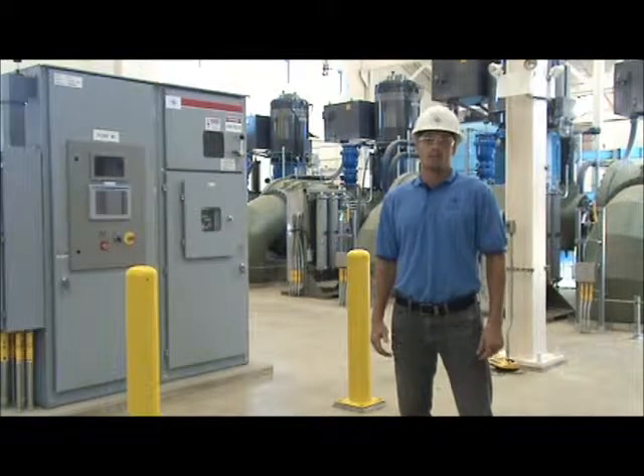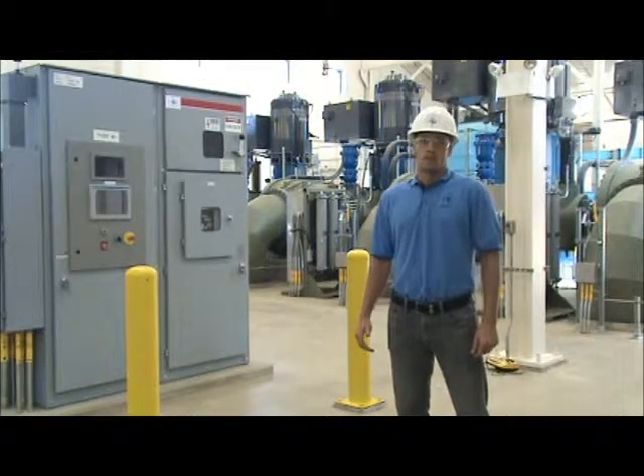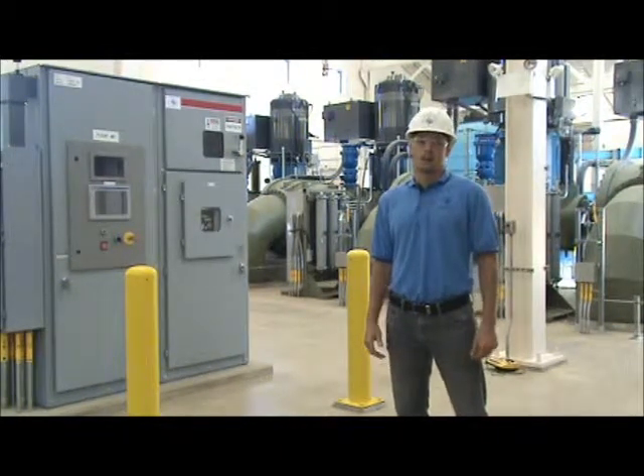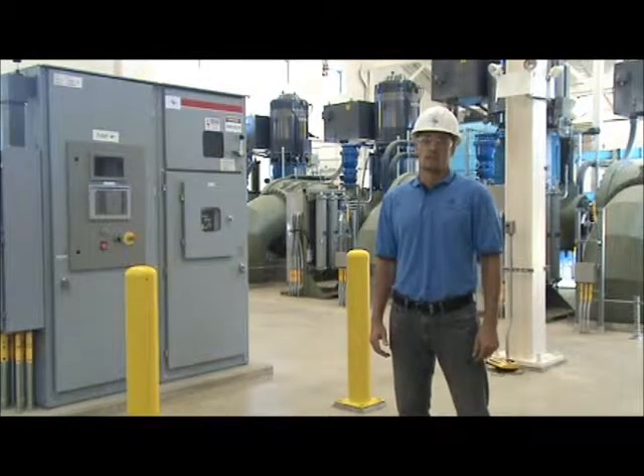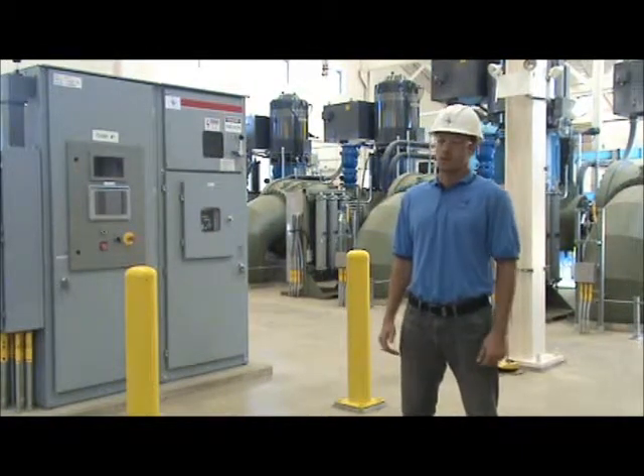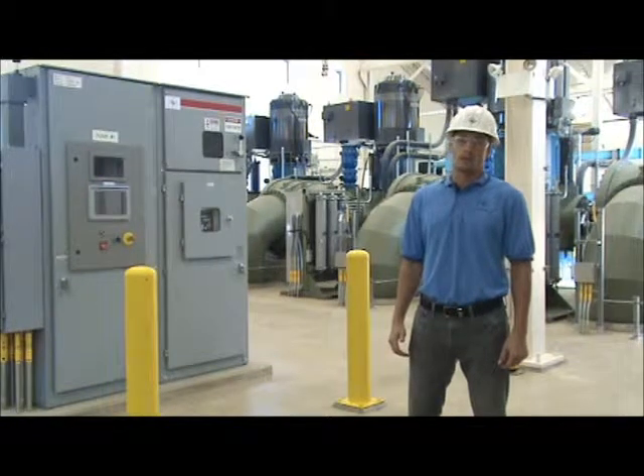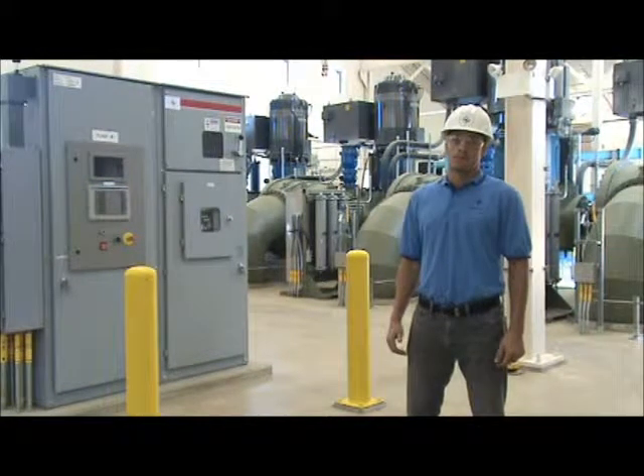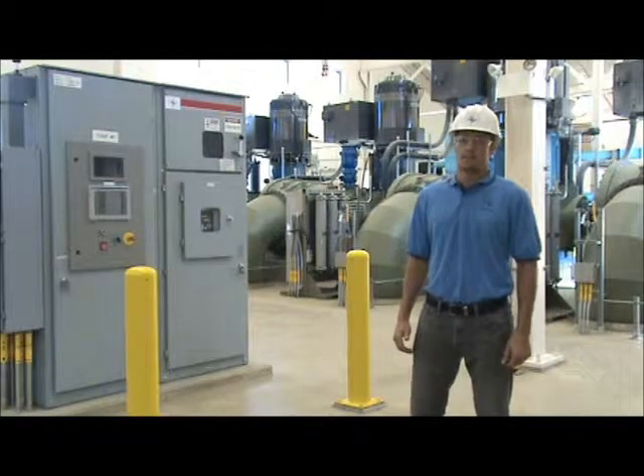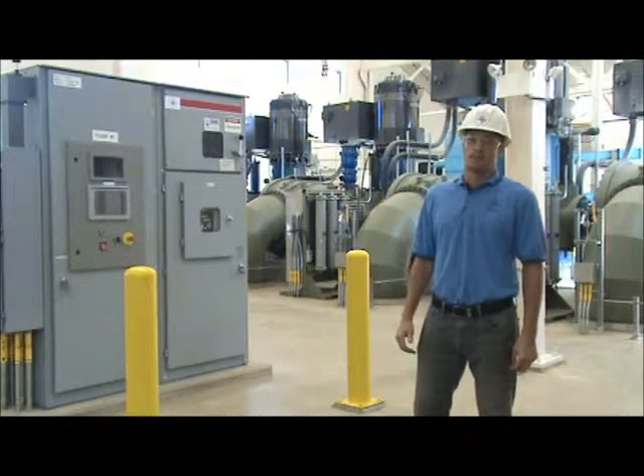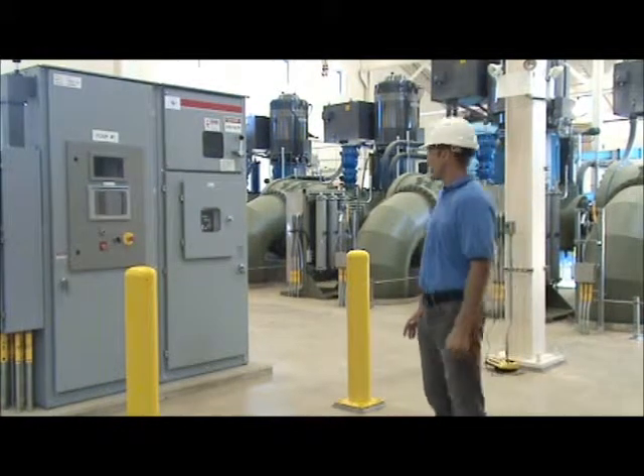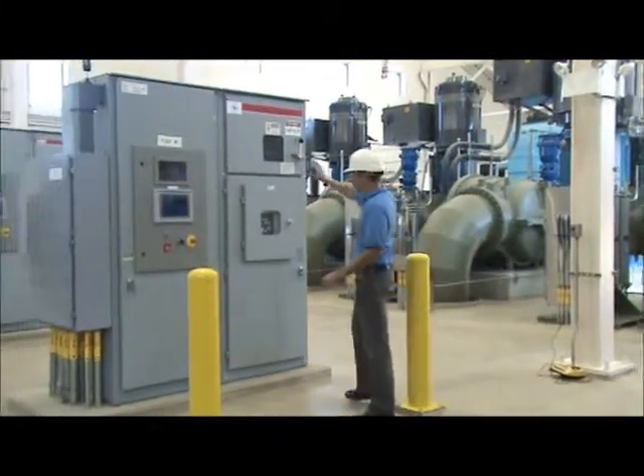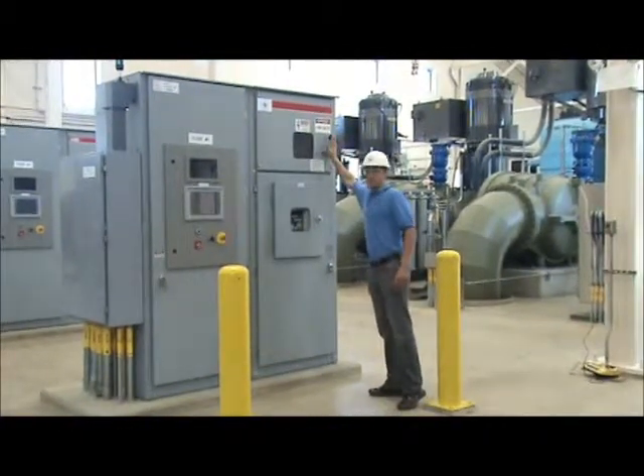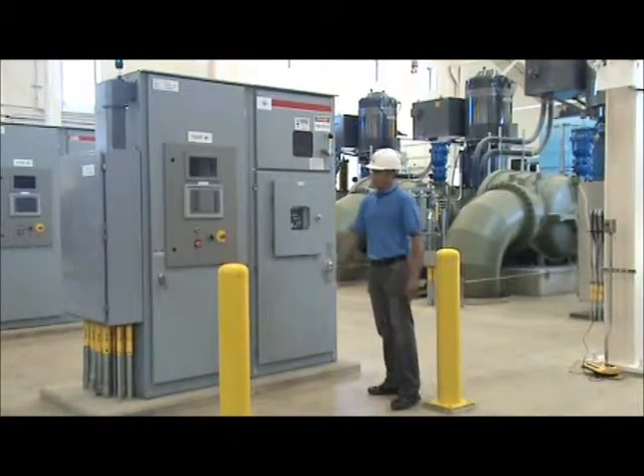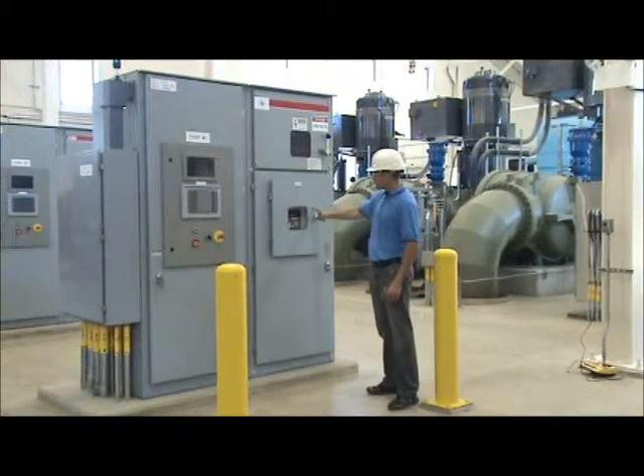The pump controller consists of a number of operating components. The main component is the 4 kV solid-state reduced voltage starter. The starter provides a controlled motor acceleration, reduced current during acceleration, and has fully functional software that provides the motor protection features. It also contains a fully line start rated vacuum bypass contactor. This component is located on the right side of the controller, and the voltage is provided through the disconnect. And then there's also 3 low voltage compartments.